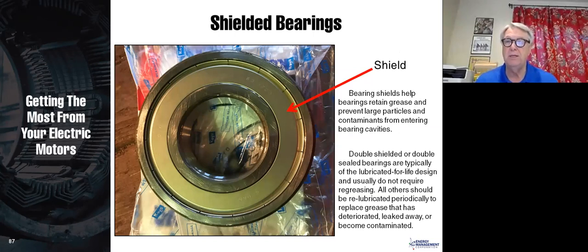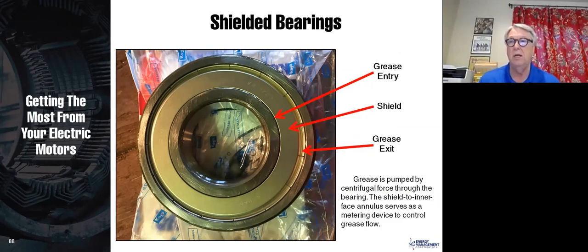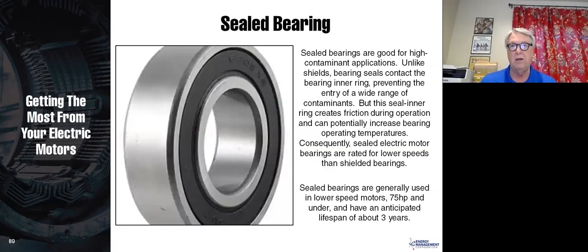We don't have too much time to get into shielded bearings, but they're double shielded or triple shielded, and that helps keep the grease in there. Even with a shielded bearing, notice that the grease still moves because there's still a little gap there, and the grease by centrifugal action will go out. It'll come out here, and then it'll go around through that grease cavity and back in. So there is some grease movement in a shielded bearing like that.